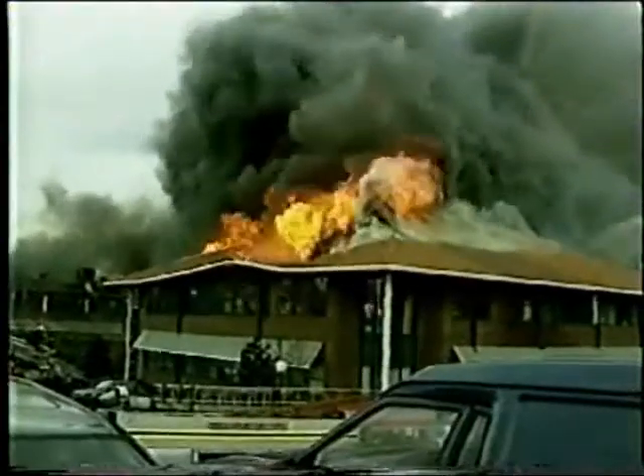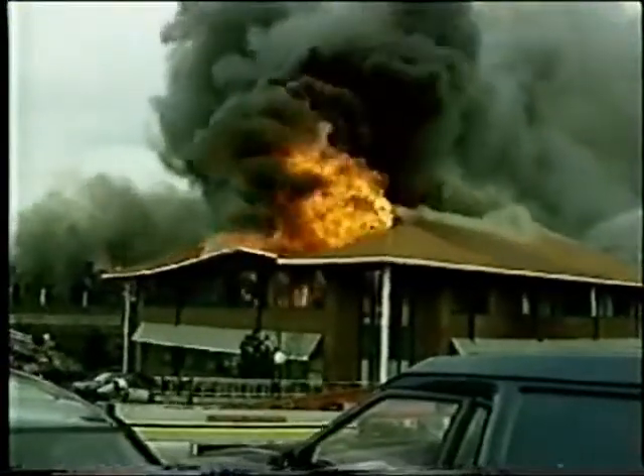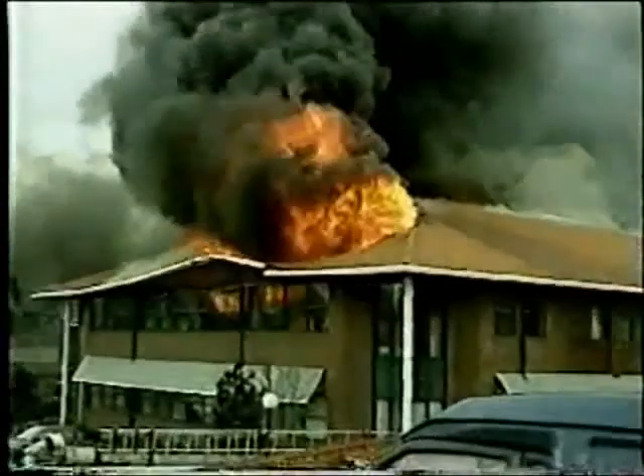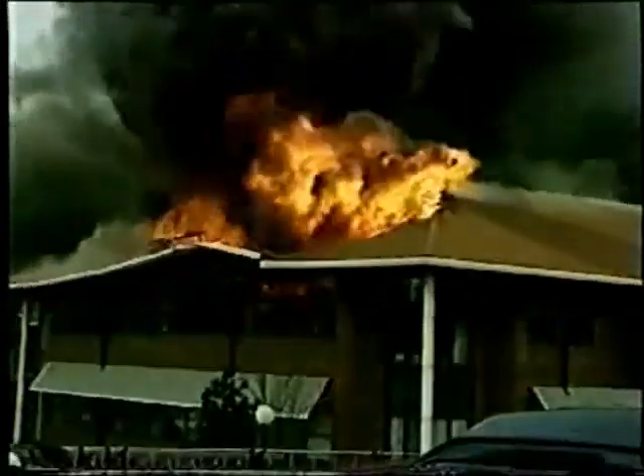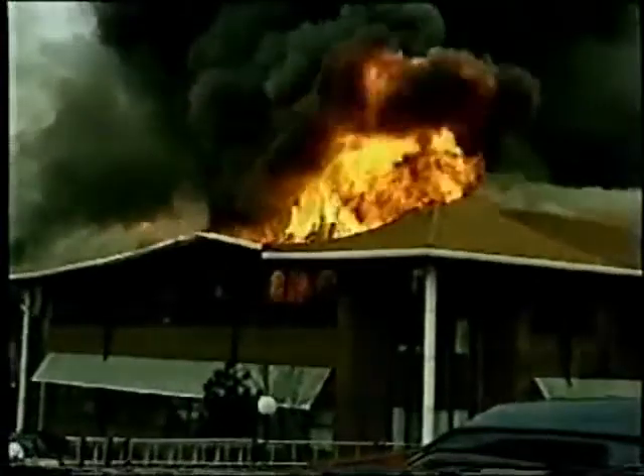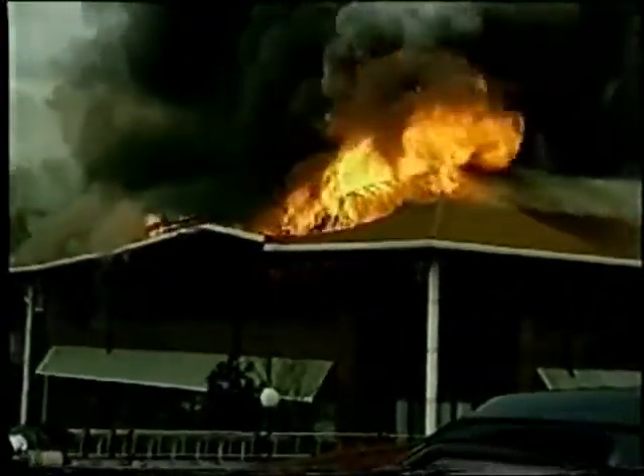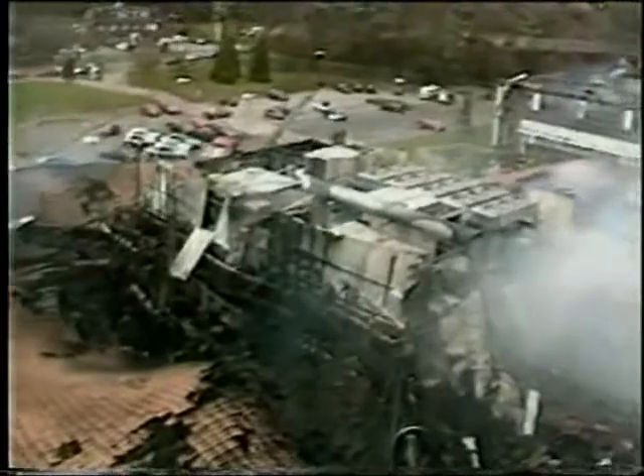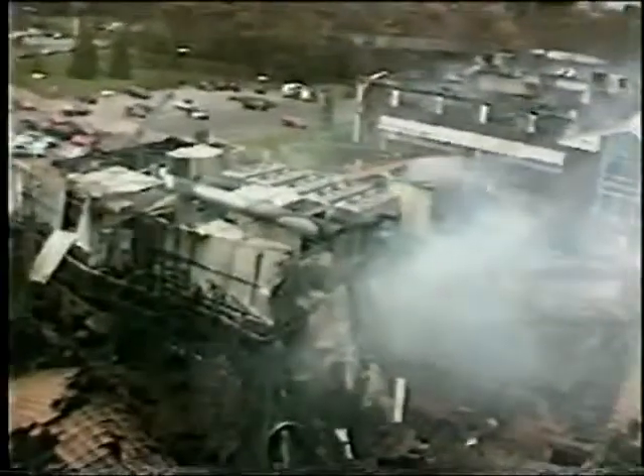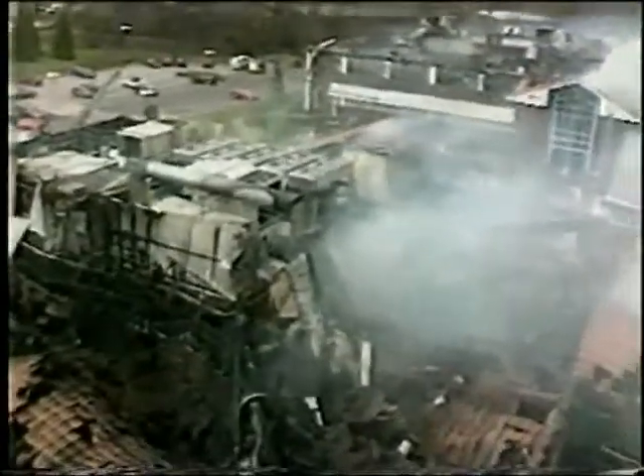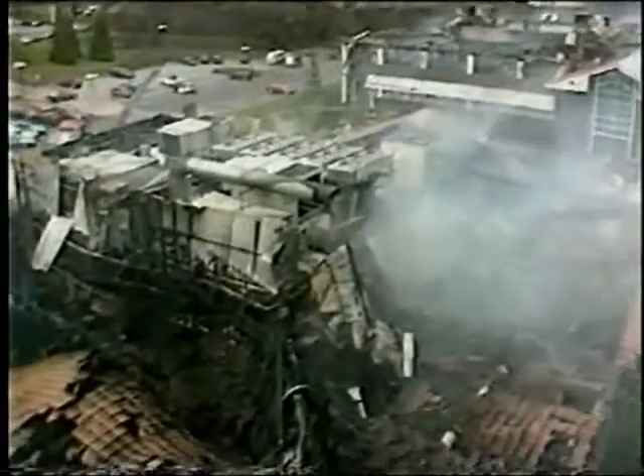When sprinklers are activated, their water cools the fire, protecting the roof and containing the flames. In so doing, it also drives the smoke downward into the seat of the fire. However, shutting off sprinklers may hasten heat release and fire spread. Therefore, it is rarely an advantage. It is extremely important that sprinklers continue to operate until the fire has been extinguished. While adequate sprinkler systems are extremely critical fire protection tools, it is essential to know how to best use them in fighting fire and minimizing loss.